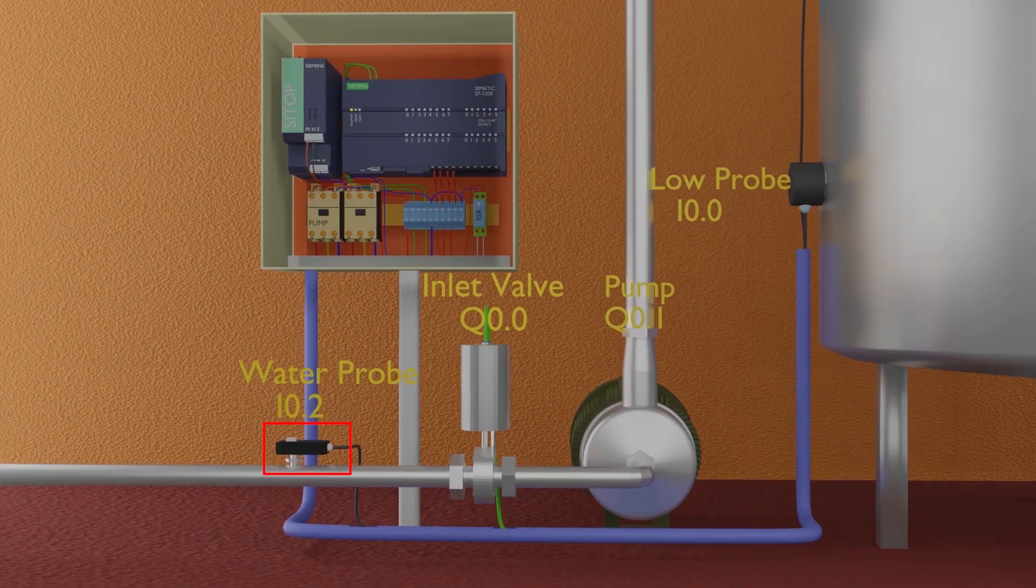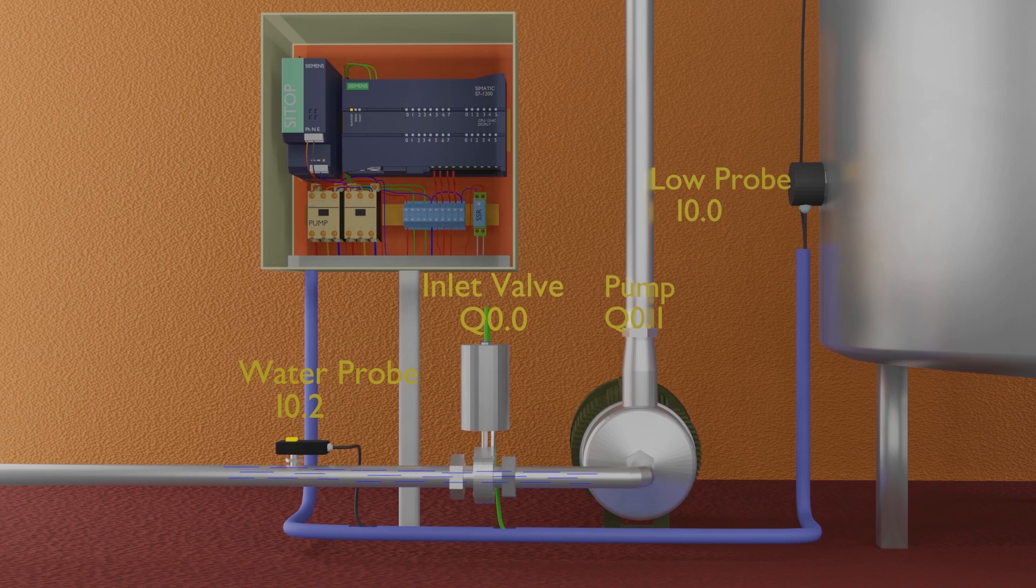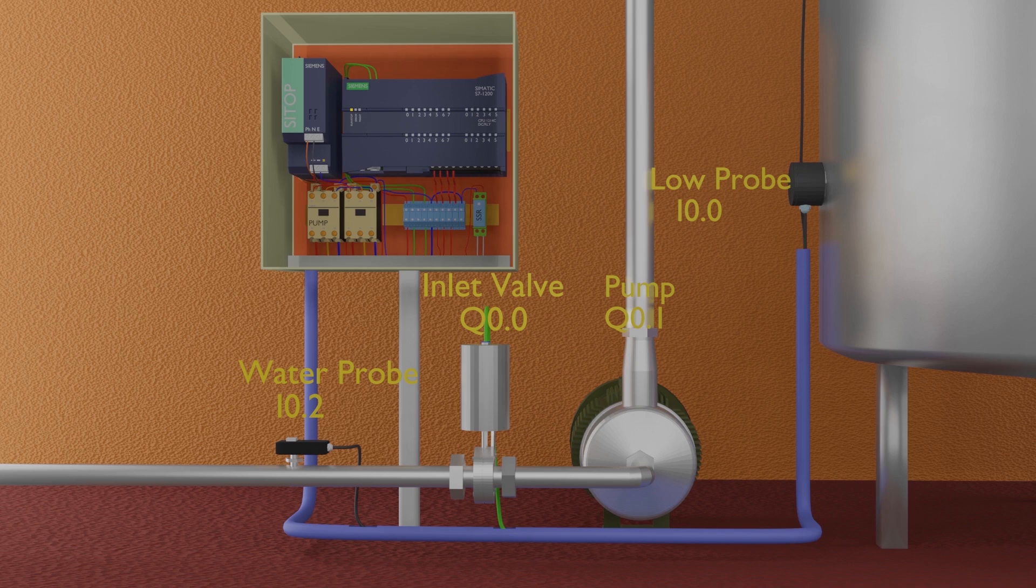There is a water level probe I0.2 installed on the water inlet line to detect the water. Water probe is usually installed on inlet supply pipe of the pump to avoid the dry running of the pump, it could heat and damage the pump shaft seals.